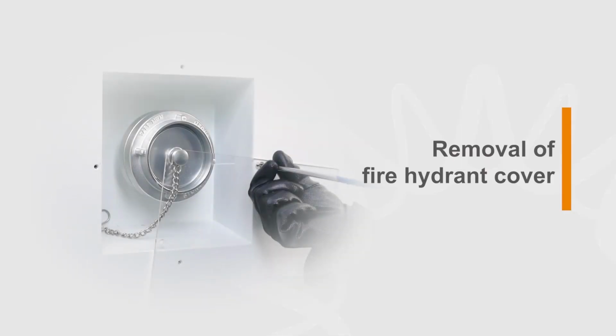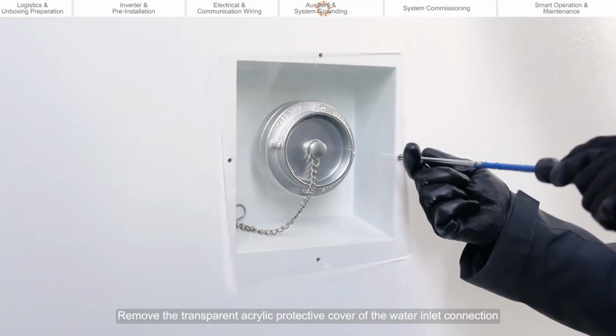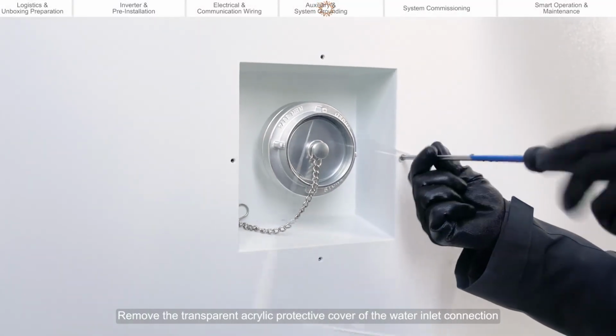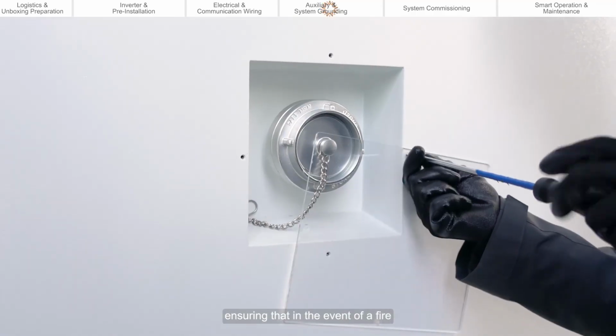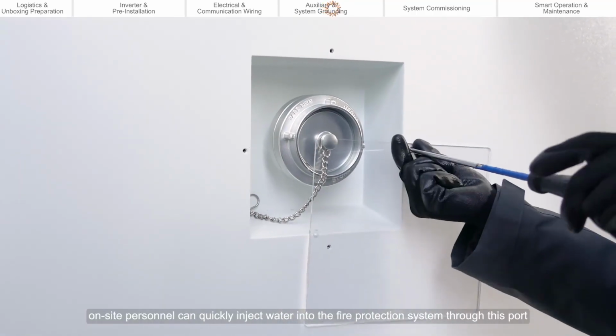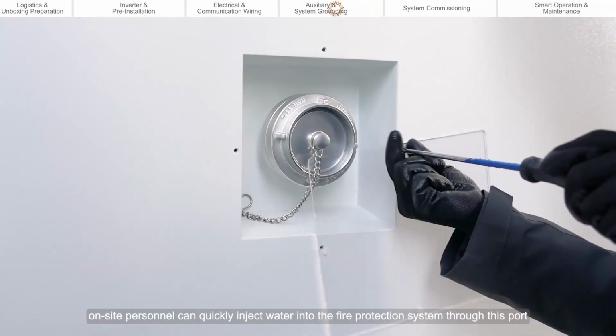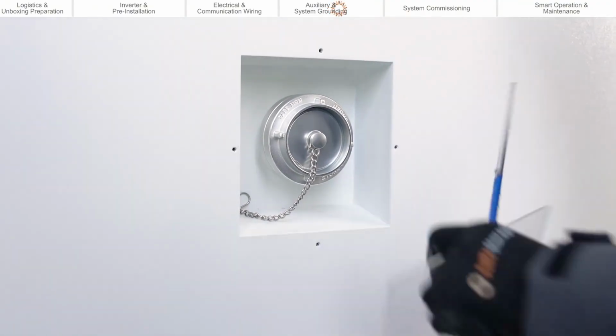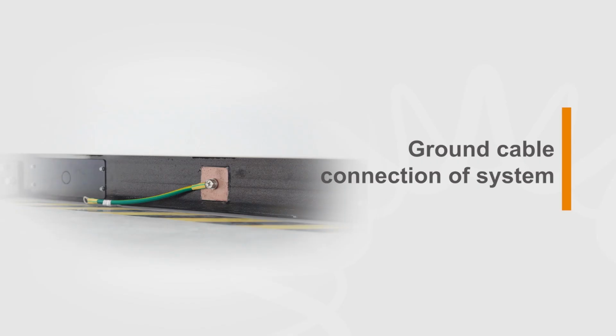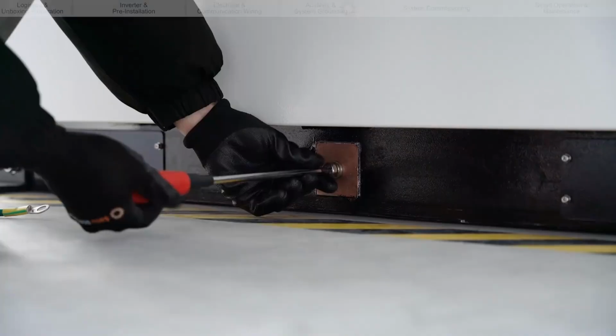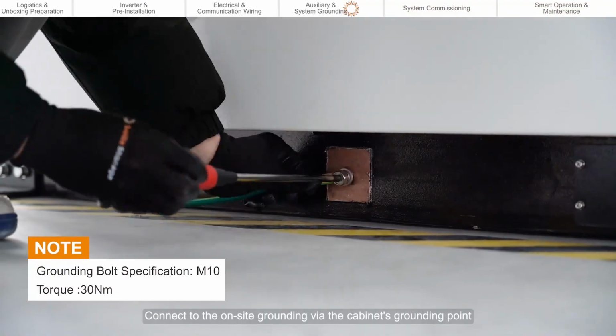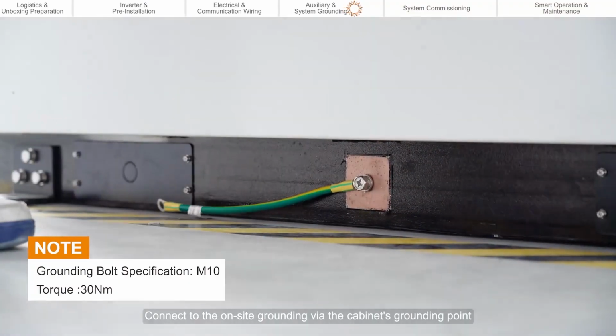Remove the fire hydrant cover. Remove the transparent acrylic protective cover of the water inlet connection, ensuring that in the event of a fire, on-site personnel can quickly inject water into the fire protection system through this port. Ground cable connection of system. Connect to the on-site grounding via the cabinet's grounding point.